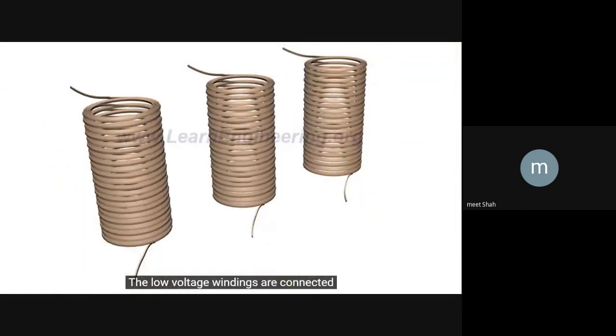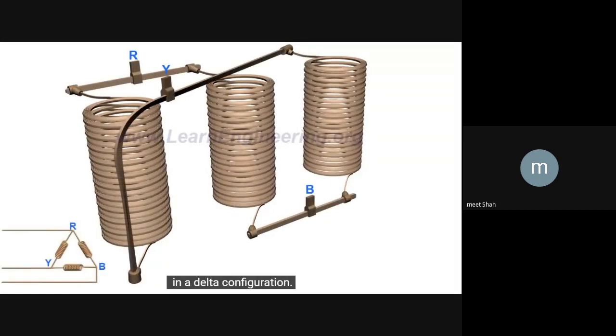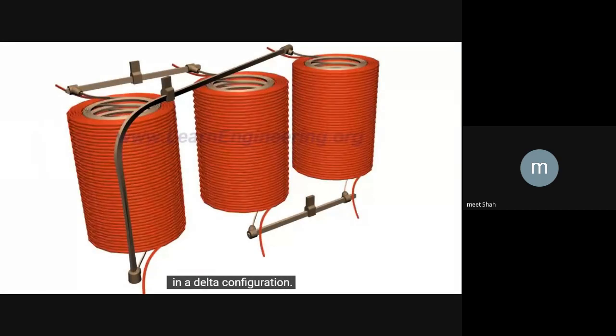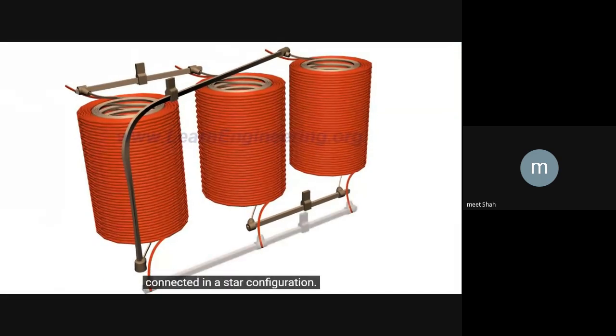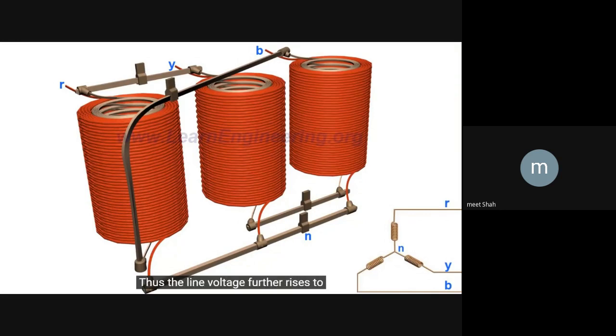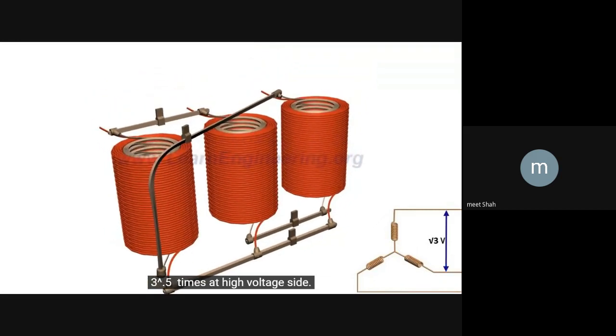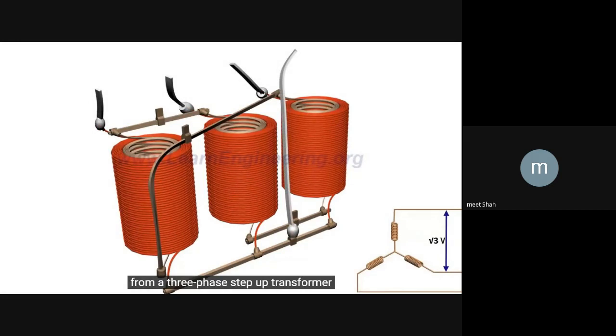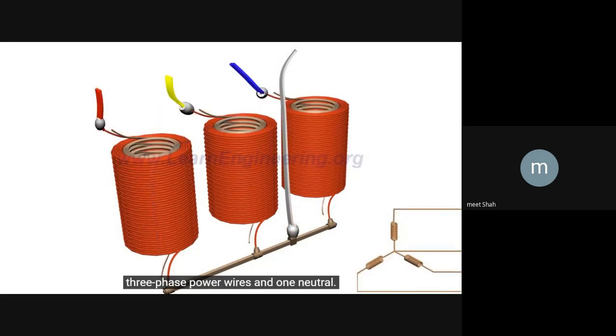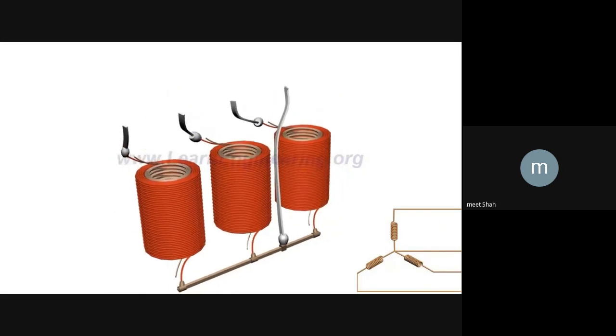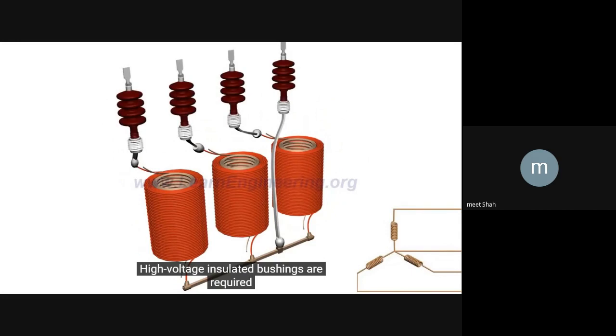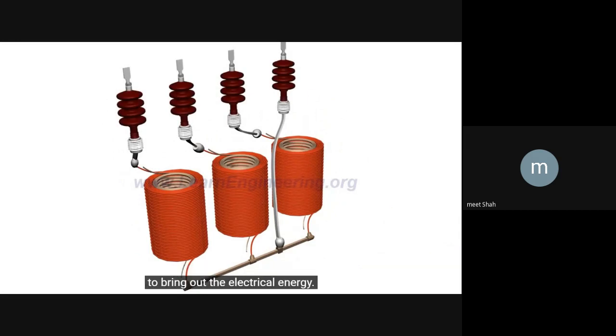The low-voltage windings are connected in a delta configuration, and the high-voltage windings are connected in a star configuration. Thus, the line voltage further rises to root 3 times at the high voltage side. This also means that, from a three-phase step-up transformer, we can draw 4 output wires: 3 phase power wires and 1 neutral. High voltage insulated bushings are required to bring out the electrical energy.